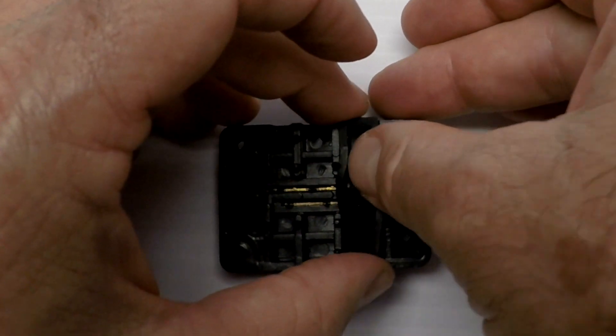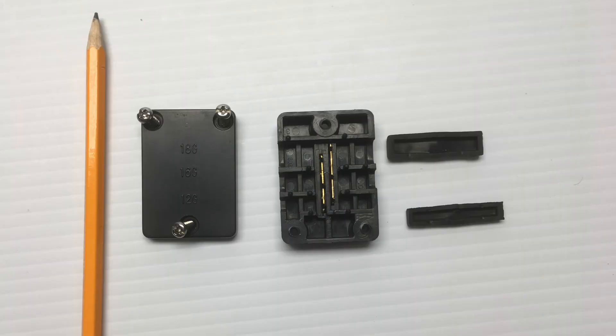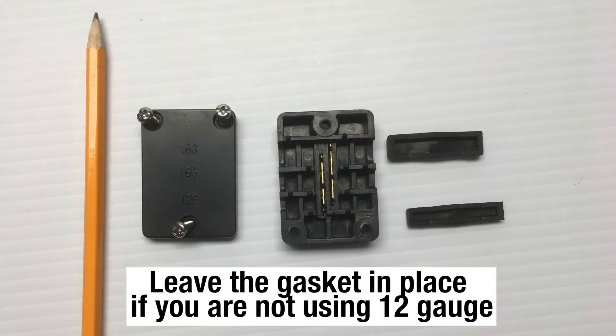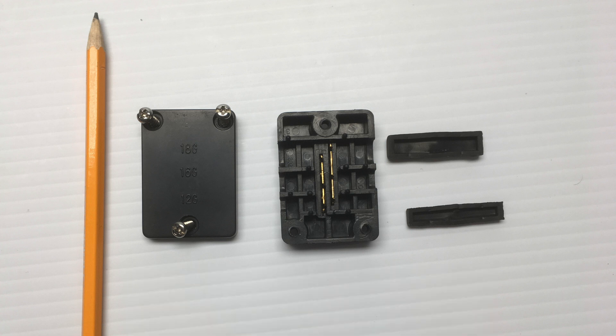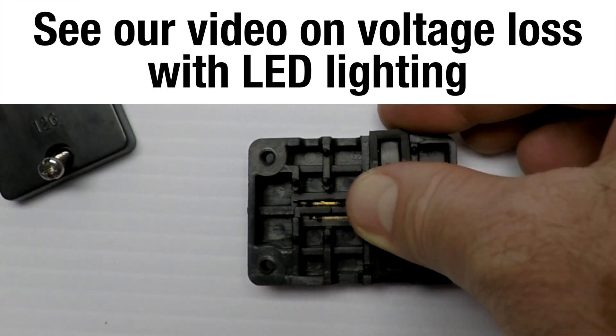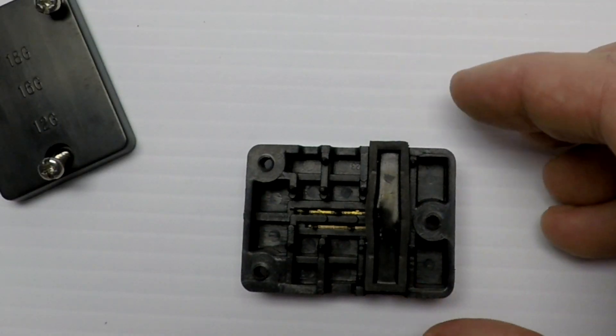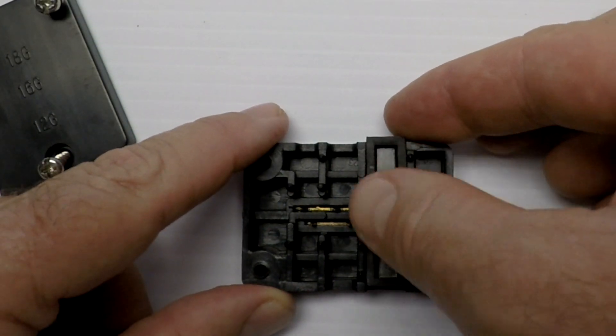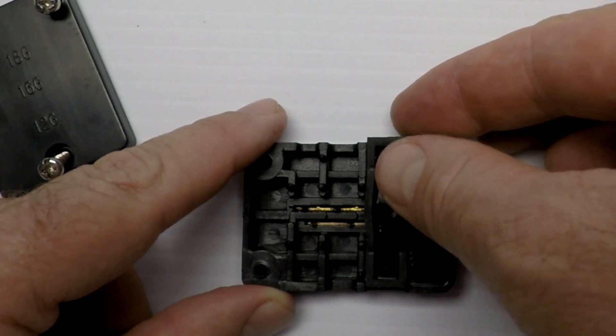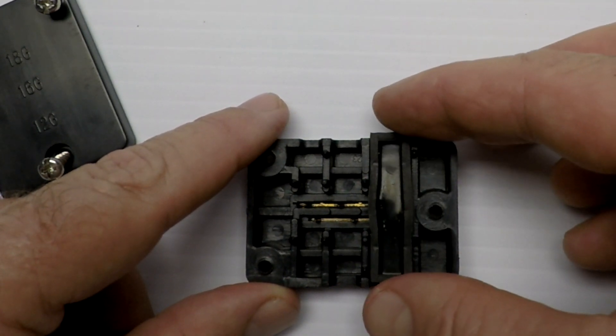We just don't need it. We don't need that big heavy wire out in the field because the LED lights are so efficient. They pull very little amperage. We don't need the big wire because there's no voltage loss really anymore. And on voltage loss with the LEDs, we actually made a video on that. So you could check that out. So we're going to leave that gasket in. If you try to press it down after taking it out, it's not going to want to go all the way, but when we put the connector back together, it will.